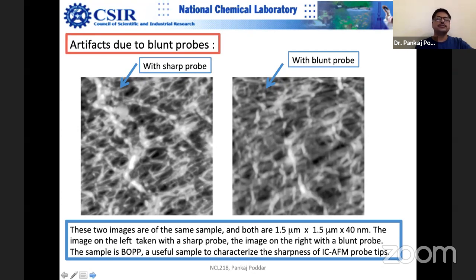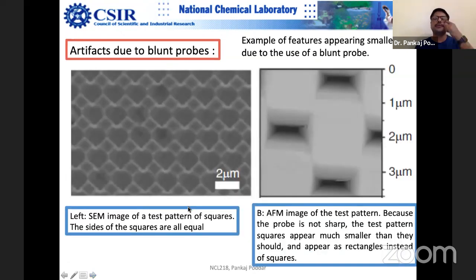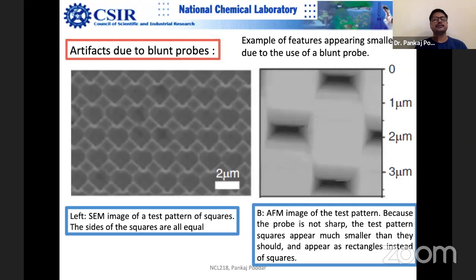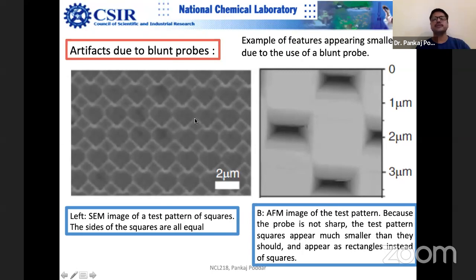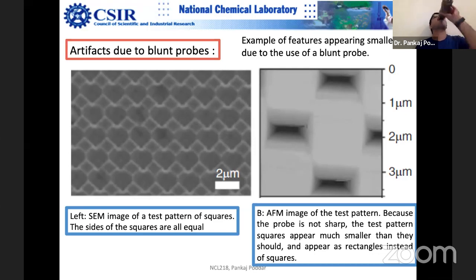You can buy test patterns from vendors — they come with calibrated dimensions in various geometries. If you do not get those dimensions, you are in a problem. Another approach: you can actually create your own test pattern using photolithography. If you have a master mask with known dimensions, you can make structures using PDMS and soft lithography, deposit some gold, and make your own pattern. Once a master copy is made, you can make many copies.